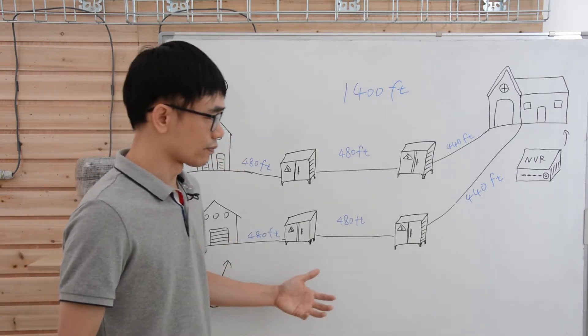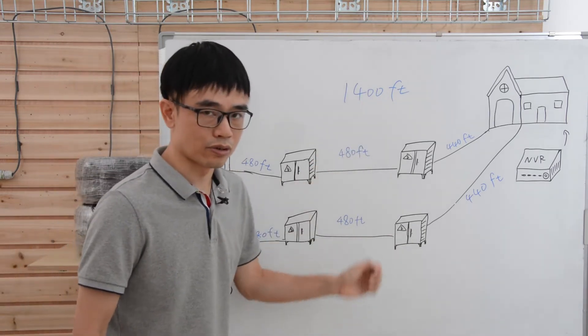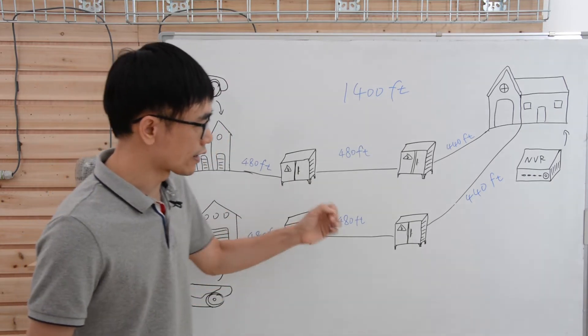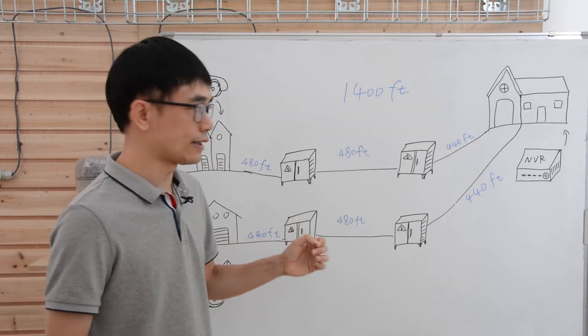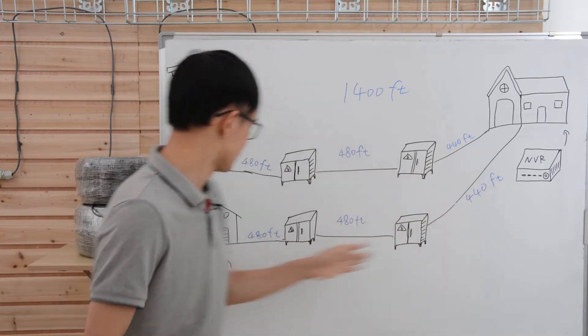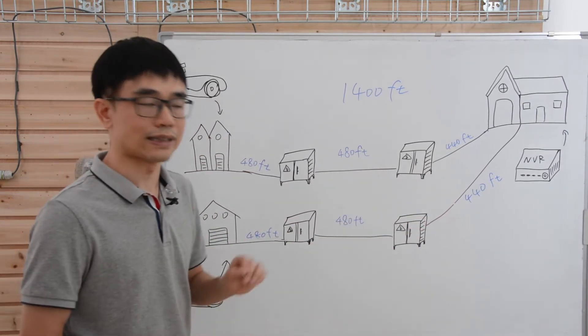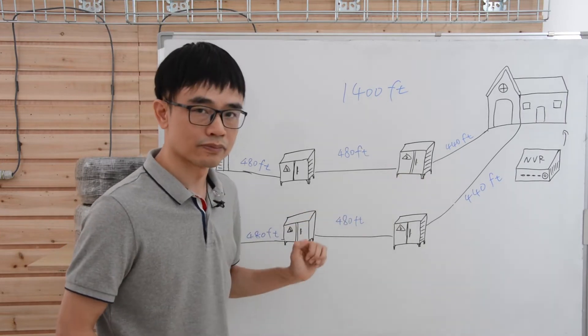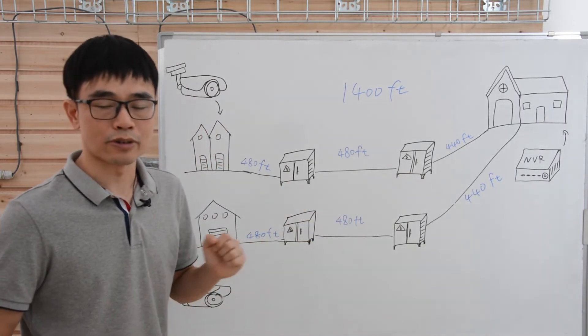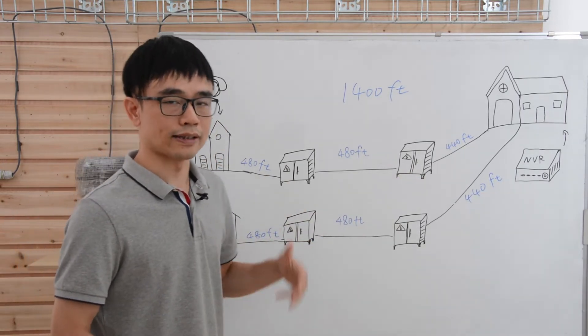Actually, we have another solution. We don't need to have all these enclosures. You can just wire a continuous run Cat5 or Cat6 Ethernet cable from the NVR to this remote location directly. There is nothing we need to place between these two. OK, now let's move to the demonstration board and see how we can get this job done.